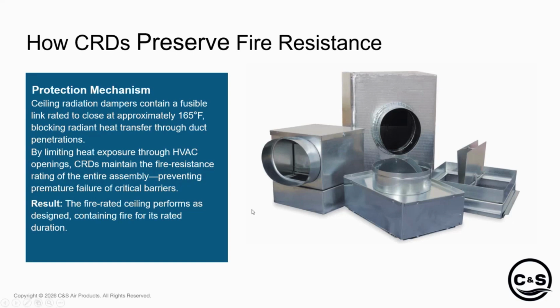And I actually got this question about a week or two ago. As long as the ceiling radiation damper isn't damaged, you can replace that fuse link without having to replace the whole ceiling radiation damper. So that's something that does come up occasionally. If a fuse link pops, you don't have to fully replace the ceiling radiation damper. You can just replace the fuse link as long as the blades are still operating correctly. But that's basically the way that a ceiling radiation damper protects the space above.